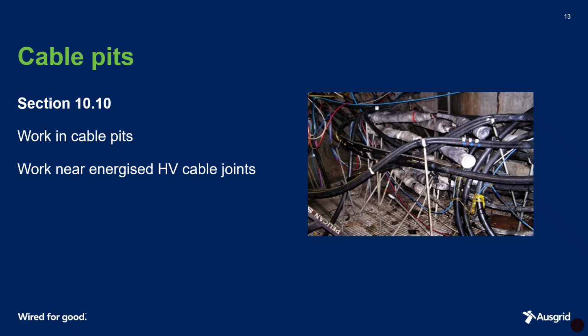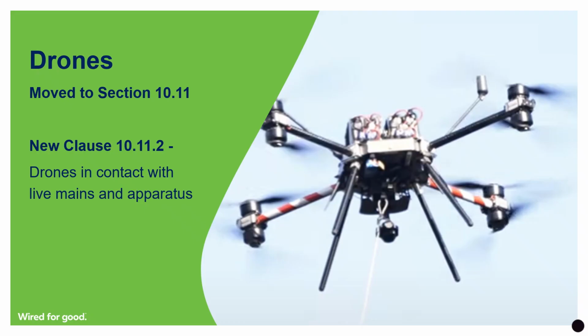In addition to including the need to be authorised to enter a cable pit, the new rules set out the electrical risk controls required for work in cable pits and work near energised HV cable joints in Section 10.10. The requirements for drone operations have been moved from Section 7.7 to Section 10.11. Clause 10.11.2 is a new clause which specifies the controls required if a drone is brought into contact with or used to attach fittings to energised overhead mains.